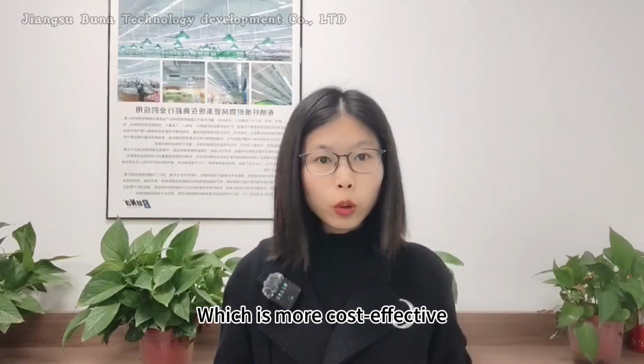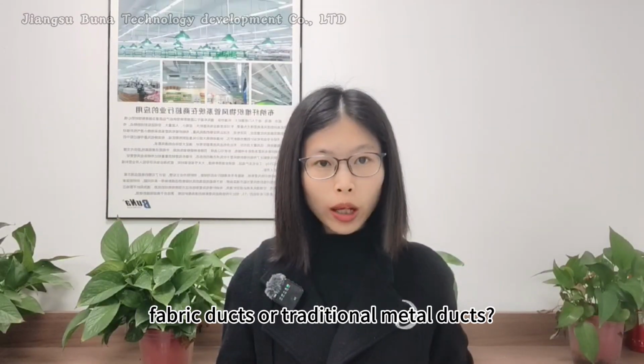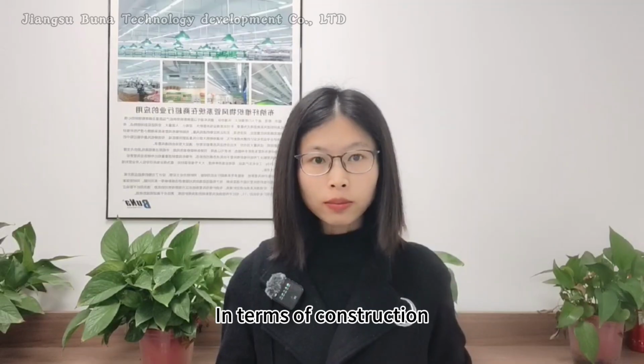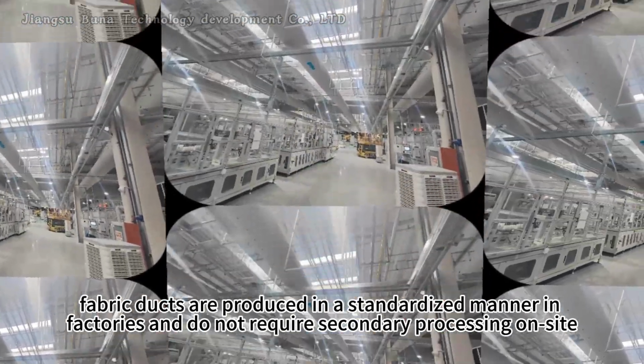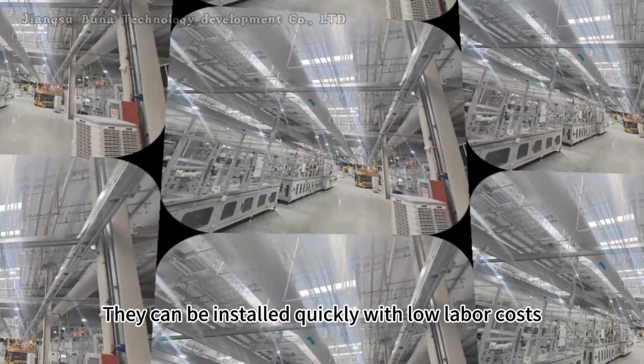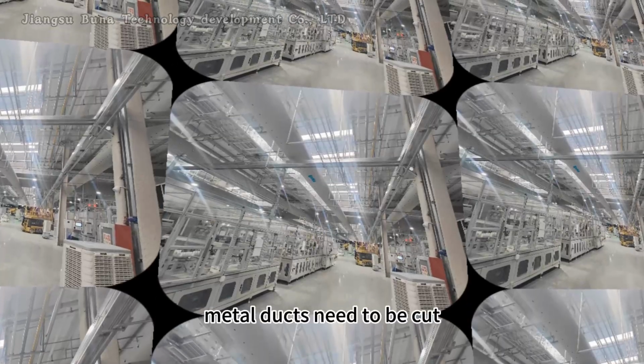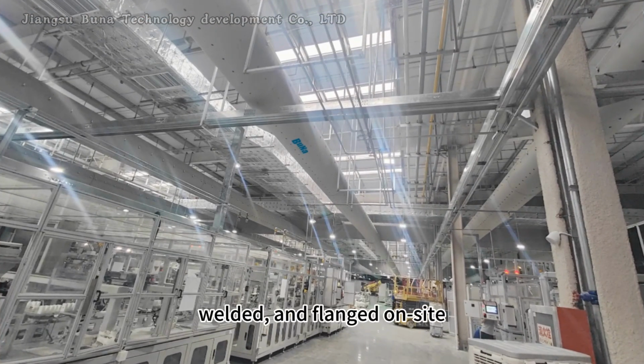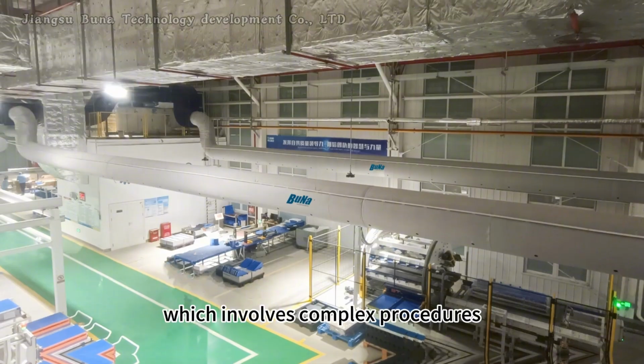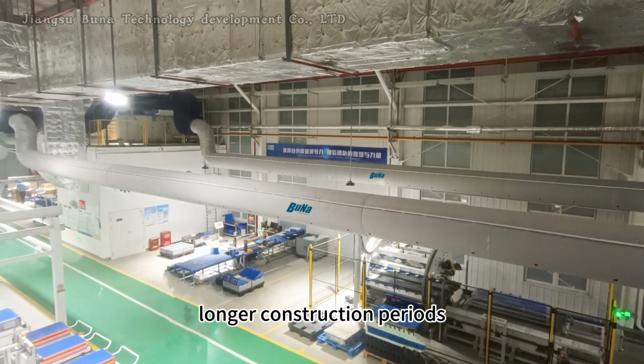Which is more cost-effective, fabric ducts or traditional metal ducts? In terms of construction, fabric ducts are produced in a standardized manner in factories and do not require secondary processing on-site. They can be installed quickly, with low labor costs.